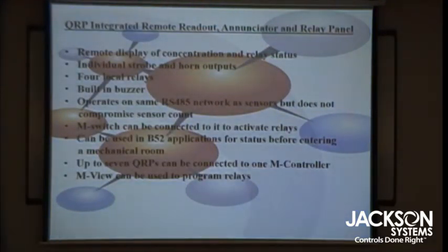We also have annunciator panels and remote readout. So you may have a remote panel in a main room, but let's say in a security office they want to see what the concentrations are. You can have up to seven remote readouts. You just place it in there, and again that works on the RS-485 network. So very, very flexible. The annunciator panel also comes with a local buzzer, a display, and relay. So if you want to turn on a local strobe or something, you can do that also.